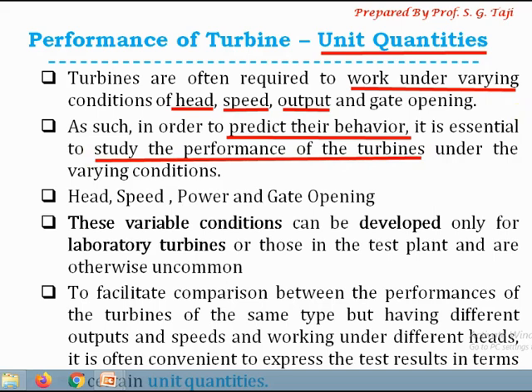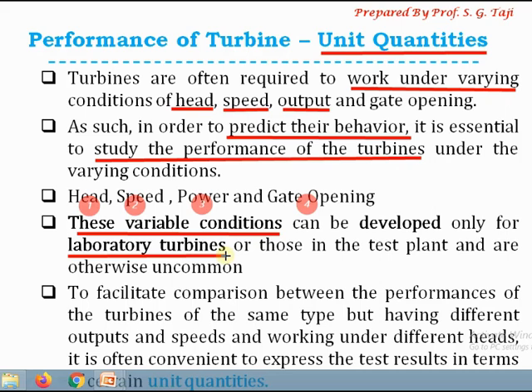For this purpose we generally consider four parameters: head, speed, power output of the turbine, and gate opening. Whenever we govern the output of the turbine, it is generally governed by controlling the gate opening. Those are the four variables which change on site, and that variable condition is developed in the laboratory, because that kind of variable condition is quite difficult to develop on the actual site. Before putting the turbine into working, we perform a test on the turbine to see how it will perform under variable conditions — for example, if the head changes from 10 meters to 50 meters, how will the turbine perform? That test is conducted in the laboratory or test plant.